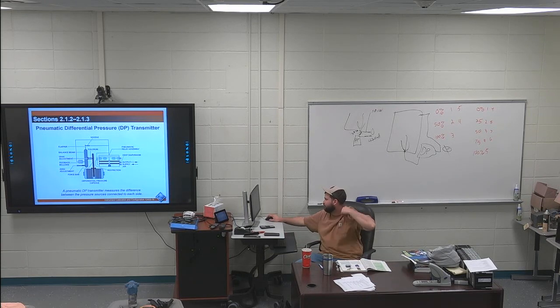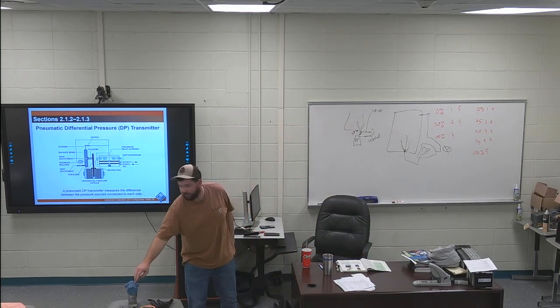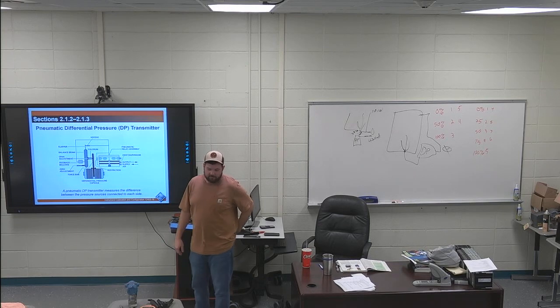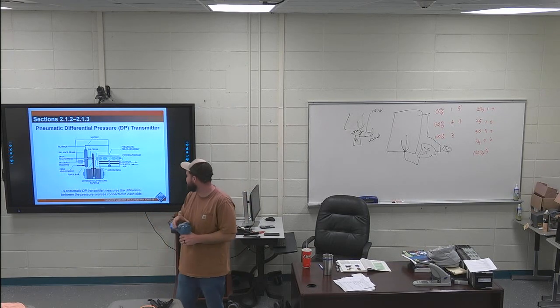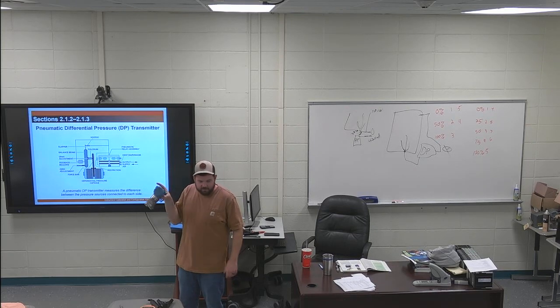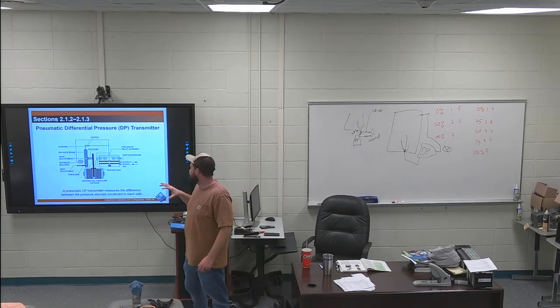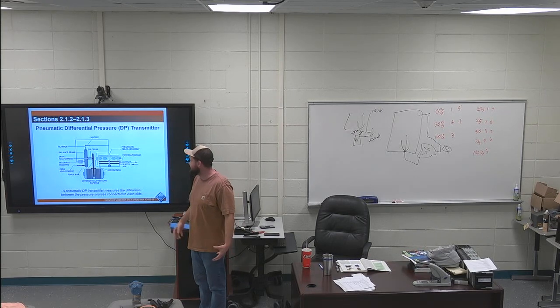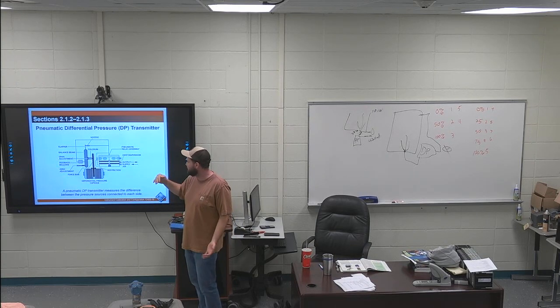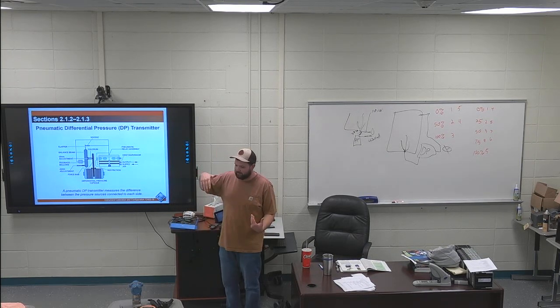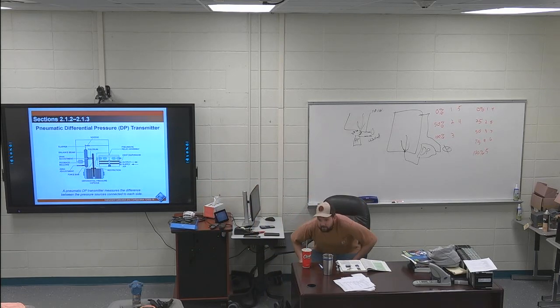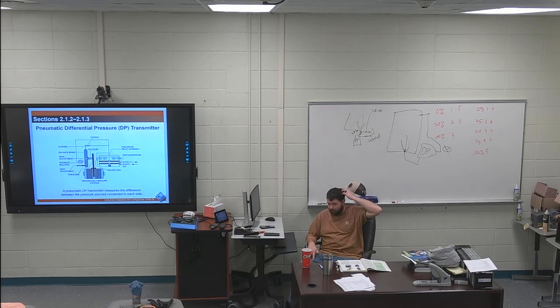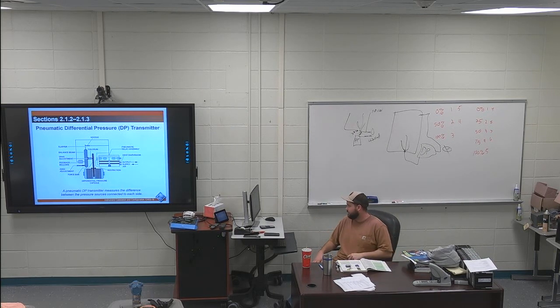This is like the inside of the differential pressure meter. To be honest, I don't talk about this a whole lot. I haven't studied this a whole lot because if the inside of this goes bad and the force bar gets messed up or something like that, you're replacing this. You're not going inside of this and messing with the feedback bellows or anything like that. So I don't go into this a ton, like the insides of how it works. You can read through and see how stuff works, and literally it's just levers and pressure and moving stuff around. But for the purposes of y'all doing maintenance, it's good to know how it works, but not super important. But you do have some highlights on how it works.